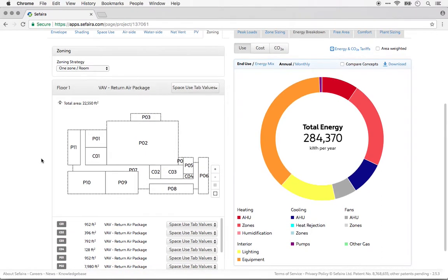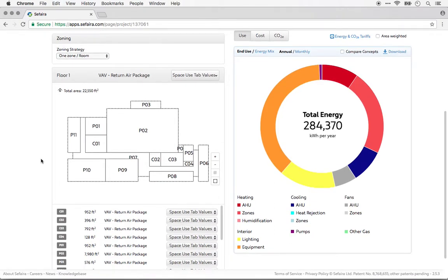And the name one zone per room is actually a little bit of a misnomer because the best practice is really not to think in terms of modeling every single room, but rather to think in terms of a zone. And generally what you're trying to do is group spaces that share a similar load profile. And that includes both internal and external loads on that space. So oftentimes that means that you're grouping together similar uses on each orientation. So in this example, for instance, I have grouped together cellular office spaces on the east and the south orientations of this building. And I can do that because they have similar load profiles. Obviously, they have the same internal loads because they have the same space use and same occupancy schedules. And on an orientation by orientation basis, they also share similar external loads. So how much solar gain they're getting or how much envelope gain and loss they have in that zone.